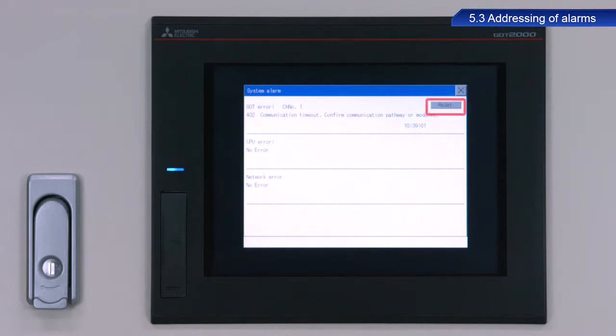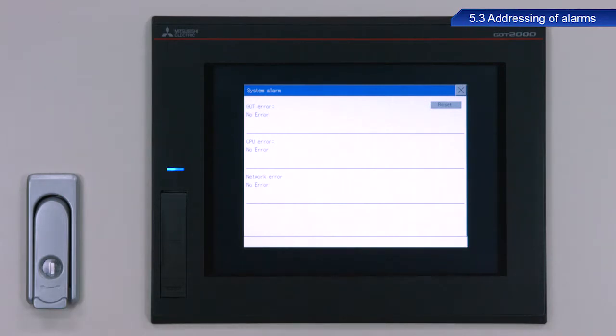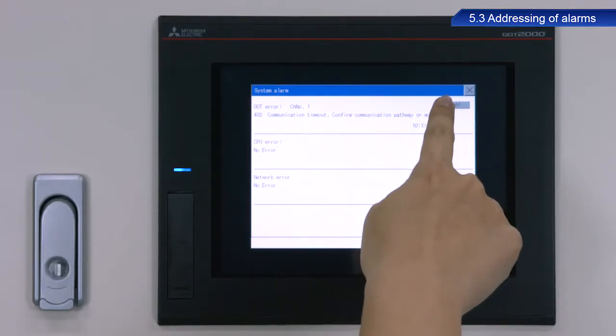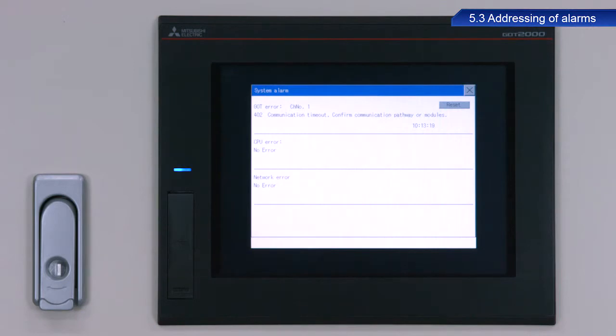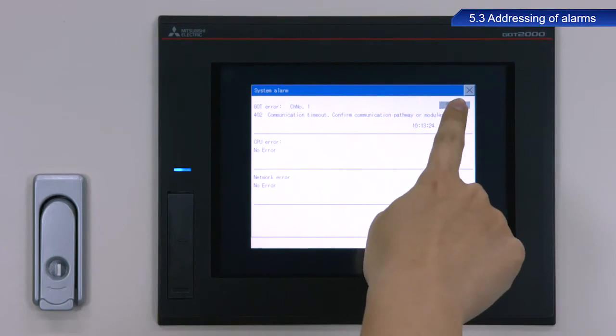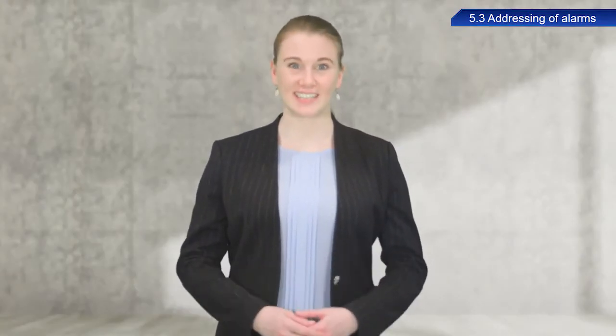Press the reset button on the system alarm screen to reset the system alarm. A note of caution: if the cause of the system alarm is not resolved, pressing the reset button will not clear the alarm from the GOT system alarm display. Double check that the error has cleared.